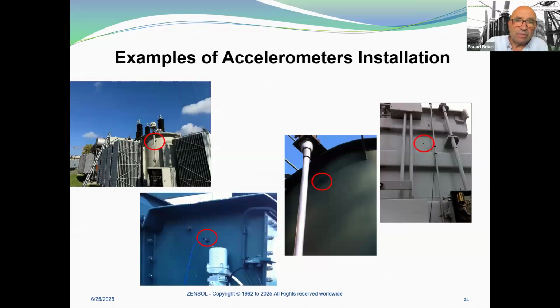Here you have some examples of accelerometer installation, and the principle is to put the accelerometer as close as possible to the diverter switch or the selector. In general, we try to put it in the middle, so that if the selector is moving and the tap change and the diverter is moving, we could get the two impacts, at a mid distance between these two parts of the tap changer.